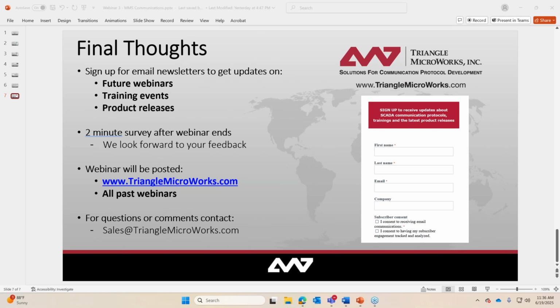I mentioned this offhandedly when I was talking about the GOOSE publisher. The reason you would want to use the simulation mode is that it's effectively just a flag in your GOOSE stream that says, I am not the actual device. You might want to decide whether you want to listen to this stream versus the actual device's stream. Well, technically it could be the actual device also publishing that stream, but it's typically sent out in a way to let devices know, I am in a testing mode right now. These should be used for testing, and it goes hand in hand with digital isolation, which includes things like actually blocking outputs to the electrical equipment, as I was displaying in the single line diagram. So you might send a phony or simulated stream of data that says, open the breaker, but you don't actually want to cut the power off to a neighborhood or a hospital or something.